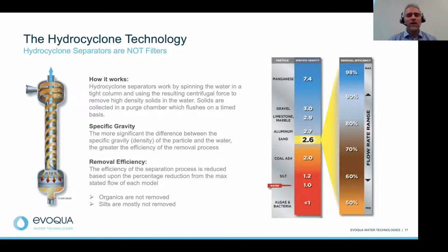So this technology is really not the best when you're dealing with cooling systems that ultimately have high levels of organics, or even very fine particle sizes, colloids, or even fine silts. Those types of particles are ultimately not really able to be removed at a very high efficiency. Overall, this technology is capable of removing about 98% of the load greater than a specific gravity of 2.6 or higher. But this technology's capability is not just dependent upon specific gravity and the particle, it's also a function of velocity of the water flow.